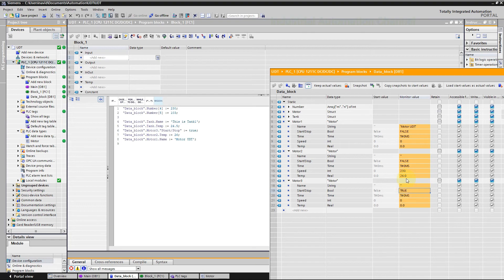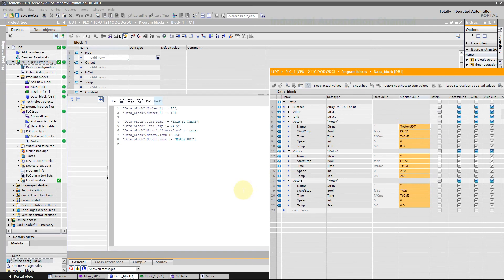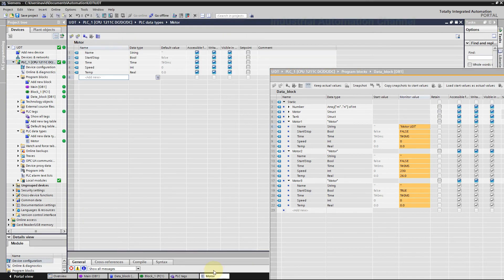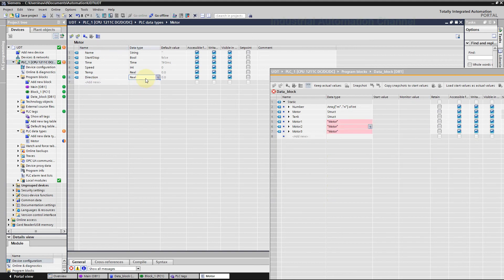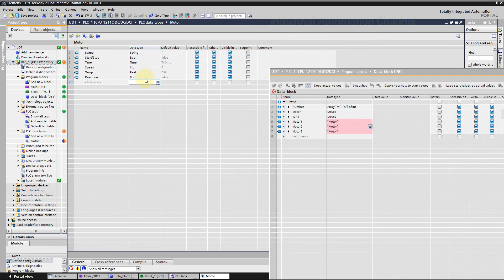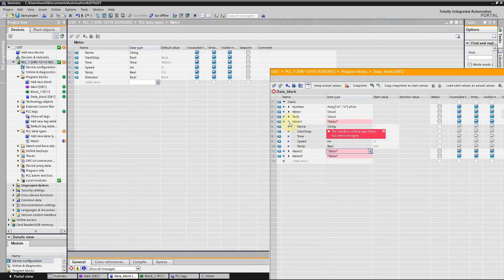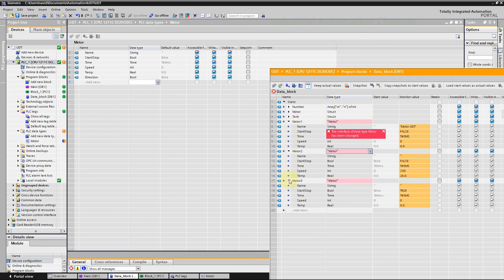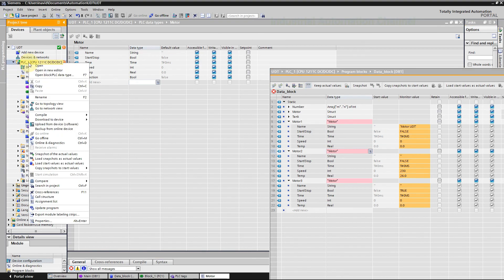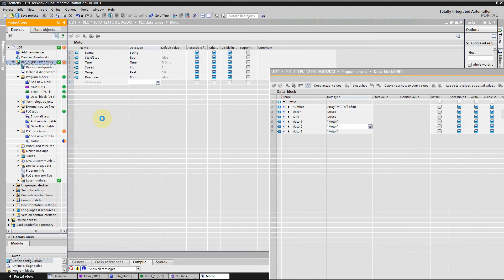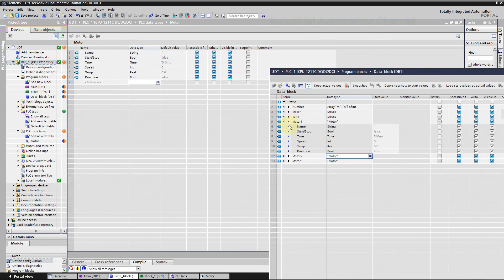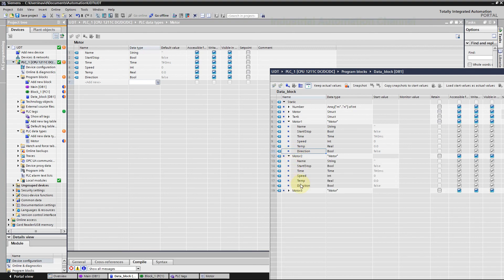An important point about UDT is that imagine after you're done with your programming you need to store another value of the motor. Then you need to add another variable to the UDT. For example, let's store motor direction during the runtime. As you see, the data type is red now because TIA detected a new variable inside the UDT. In this case you don't need to delete anything and create a new UDT, just click on PLC and compile the program software and rebuild all the blocks. If you go to the data block you see the new type is added.